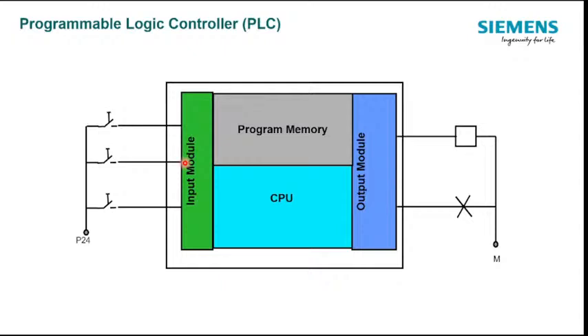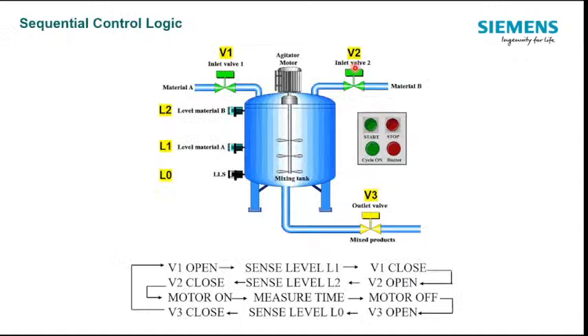So whenever level 1 has been reached, I will write a PLC program in such a way that I will be closing V1 and opening V2. V2 will be connected to the output module, and this L1 limit switch will be connected to my input module as an input to the PLC.